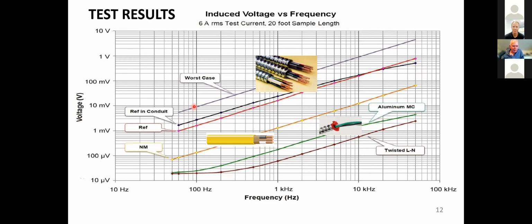Now the worst case comes from having the ground wire right next to either neutral or line, but having it close to one and as far away as it can get in a given conduit from the other. And predictably, that gives the highest voltages. So you can see here with a 6 amp RMS test current - this again was an audio power amp with a dummy load - had 6 amps of current over a 20-foot sample length.